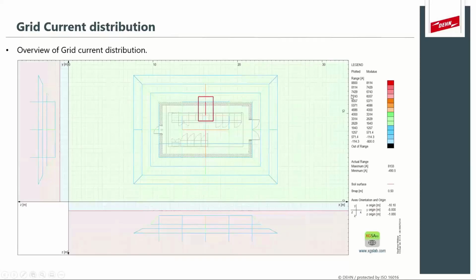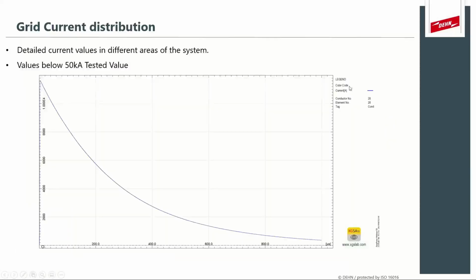focus on the conductor that carries the most current, which is said to be 8.8 kA. And if we do that same time domain calculation on that conductor, we see it's a little over 10 kA. So that's the difference. But the main point is that in both cases, we didn't come near the 50 kA tested value of the component. So we know that none of our clamps that we use to connect the grid will be overstressed.